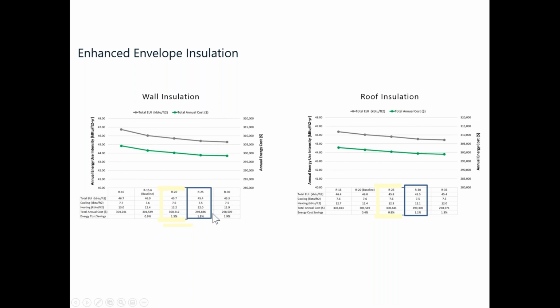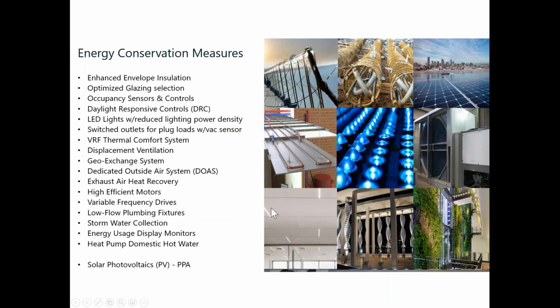We picked R25 for the wall and R30 for the roof insulation, and the total annual cost delta if we kept going is quite small—less than $1,000 in annual savings by improving insulation further. More insulation is always better, but at what cost and what return? At some point you have to draw the line and say I'm not going to spend an extra dollar per square foot in insulation to save $800 a year. It really didn't have a payback, so we took that money and applied it elsewhere in the building.